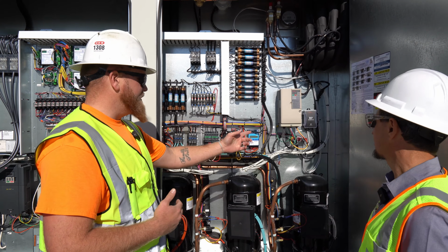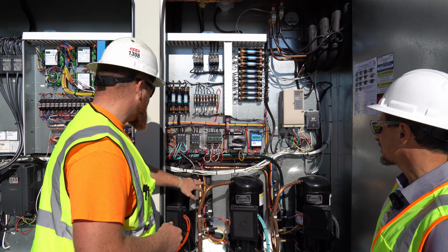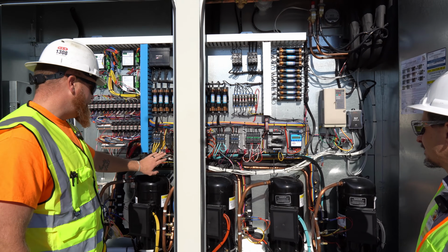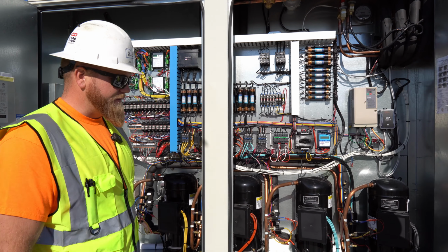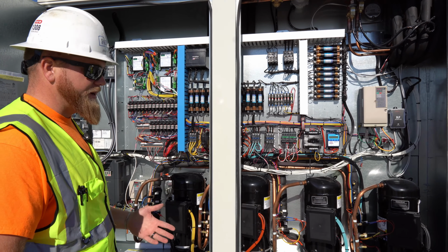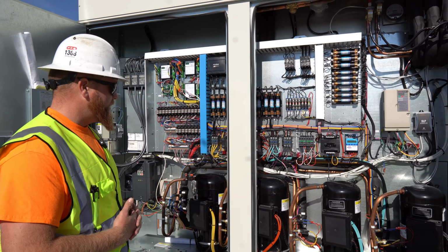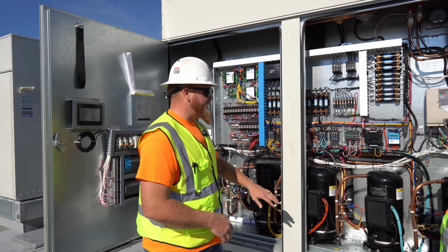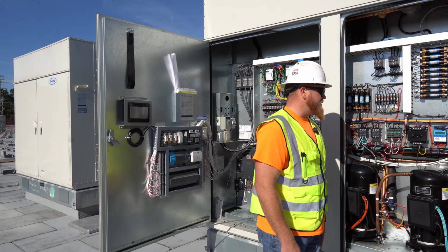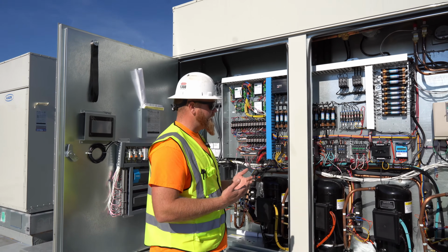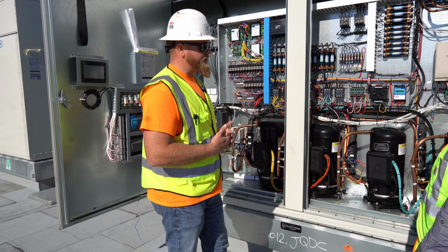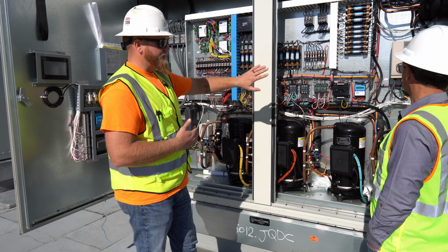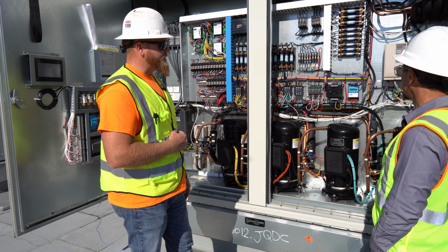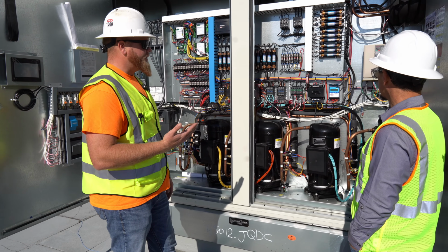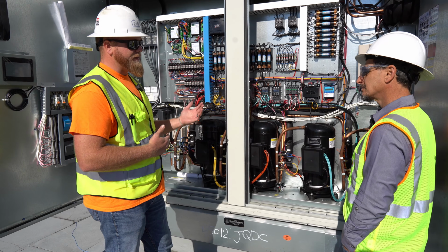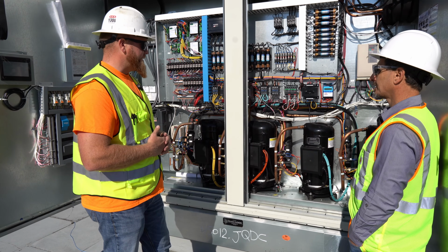Yeah. And we use that same CT for all of our compressors. So we've got one on every load side coming off of the main contactors to verify that we have compressors turning on and turning off when our controls are telling them to. We do have phase and brownout monitoring on these systems, so we can monitor if they have a phase loss, a brownout, high voltage, low voltage. We try and keep those pretty standard with parameters set by the VFD manufacturers, so we don't go over voltage or under voltage. We try and protect our motors to the best that we can.